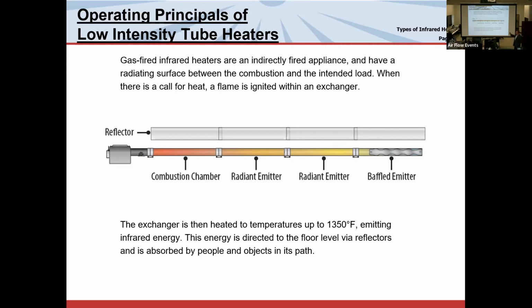Because the common challenge that we have, and I'll come back to this, is that that first tube is hotter than the last. And people think the heater isn't working properly, that it should be perfectly even. It's not. But when we design them, we are trying to figure out how to manage that. The other thing is the length of the heater is often a function of how much energy we're putting down it. If I have 50,000 BTUs, I may only be able to go out to 4 pipes. If I have 200,000 BTUs, I can go out to 9 pipes. Okay, so it's a function of how much energy in, so that when we get to the end, we're in the target window that we need to be. Next slide.